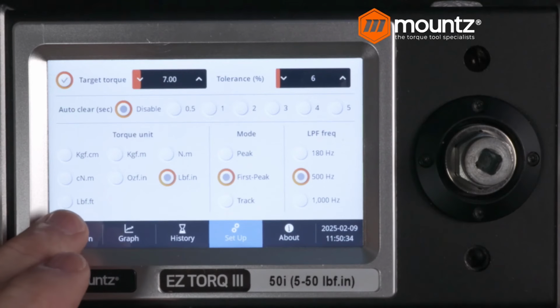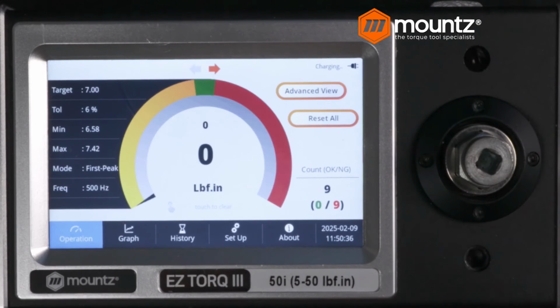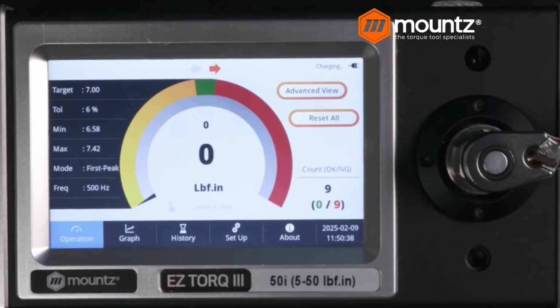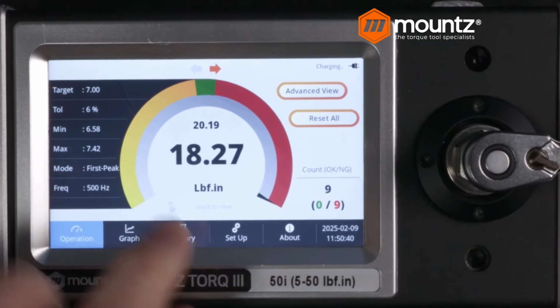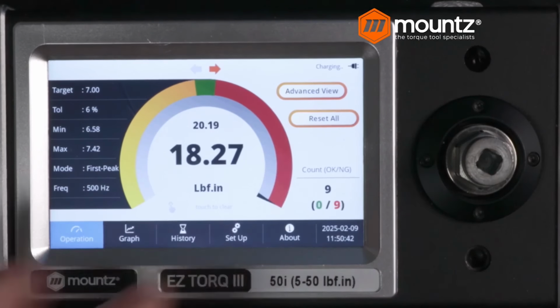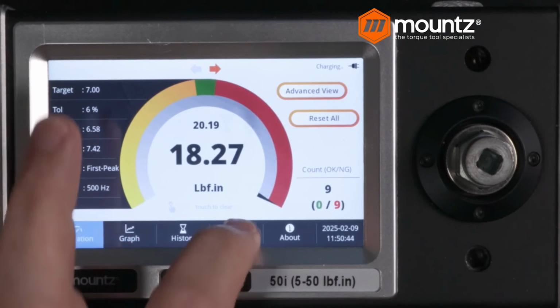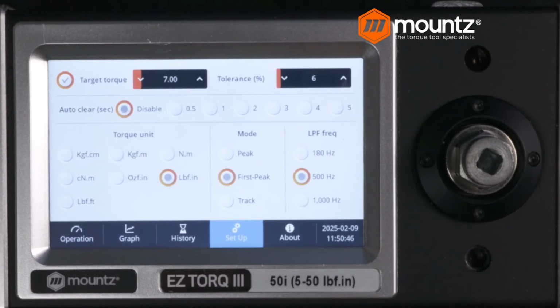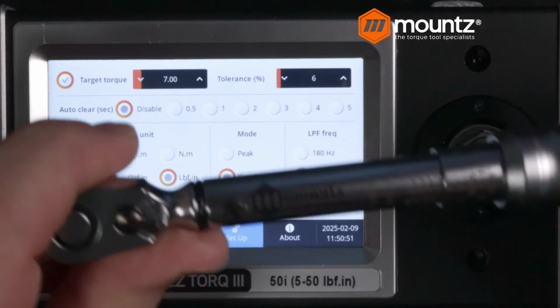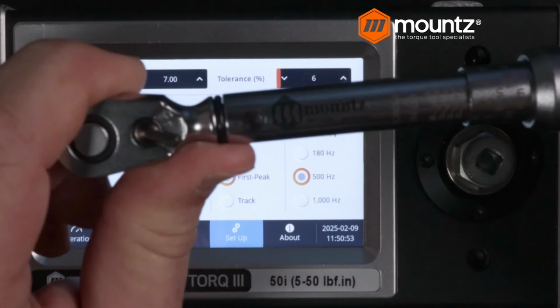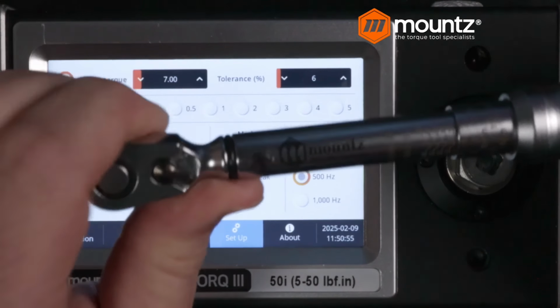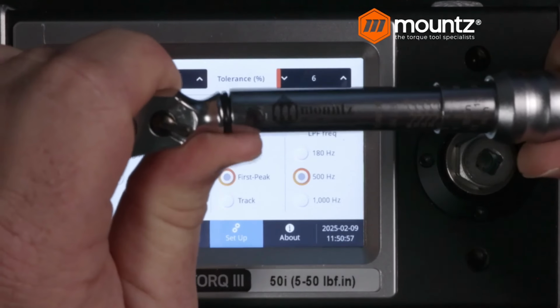And then we can go ahead and go back to our operation screen. And I think we're somewhere in a ballpark around 18 inch-pounds or so. Yep. And so what's unique about the first peak mode is that it allows us to capture the value at which the wrench will reach before or when the click happens.